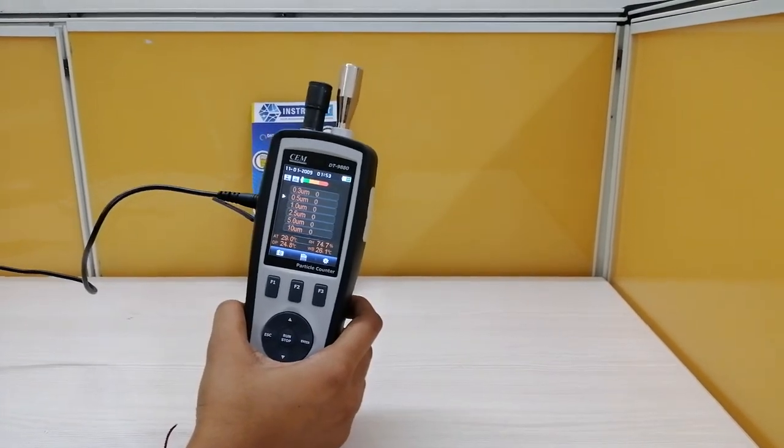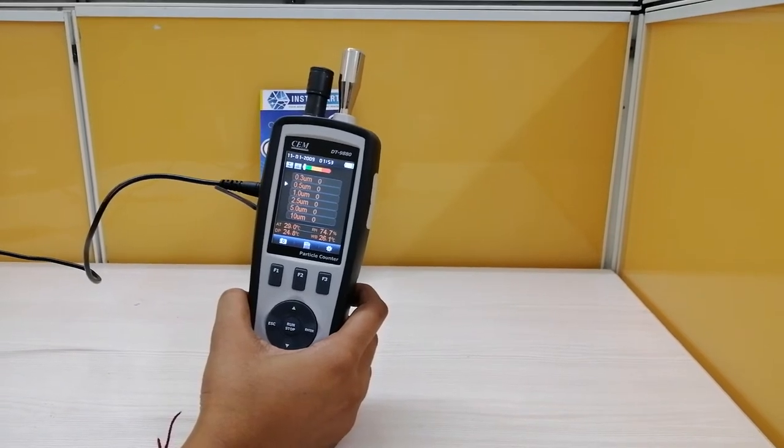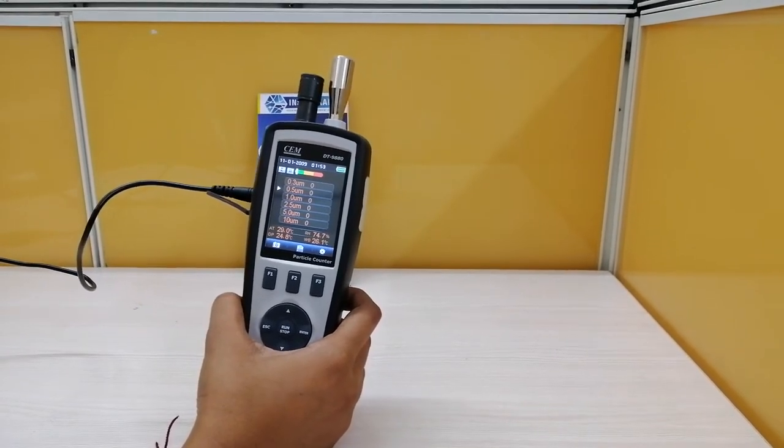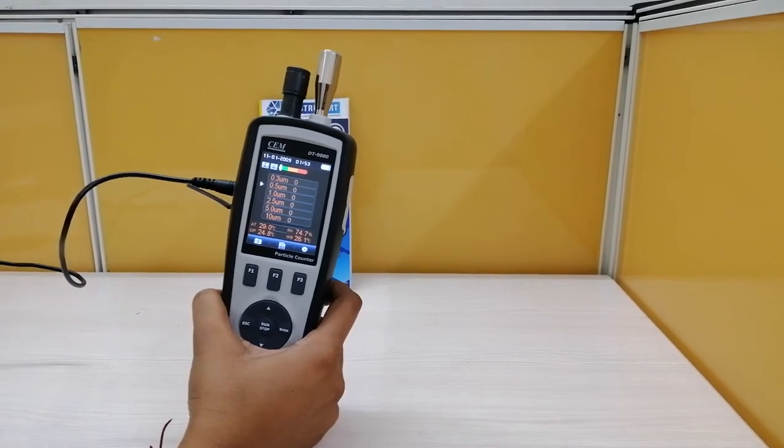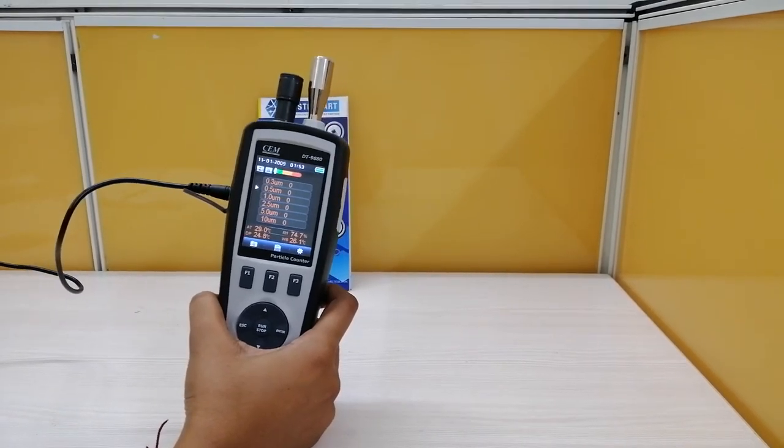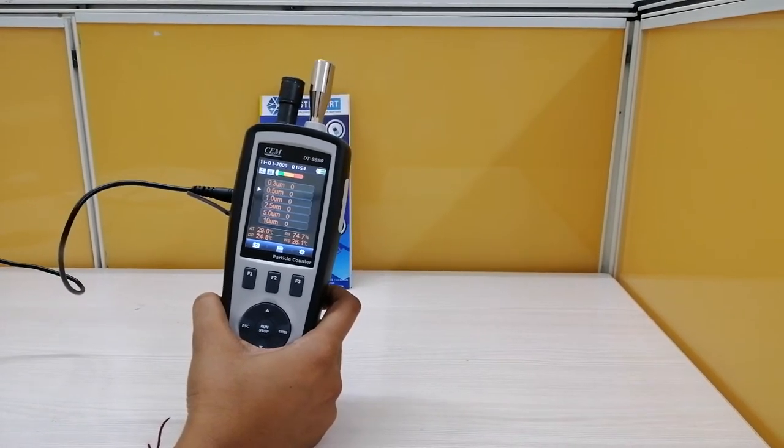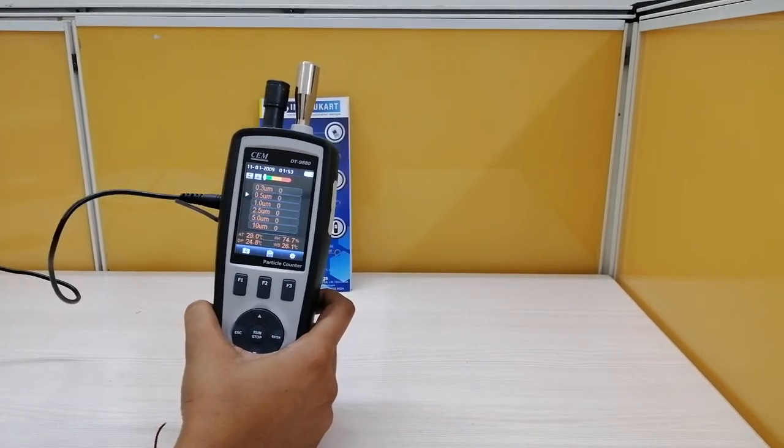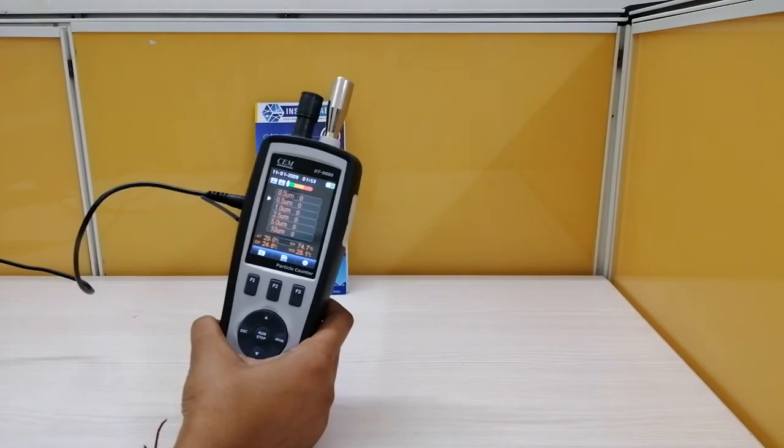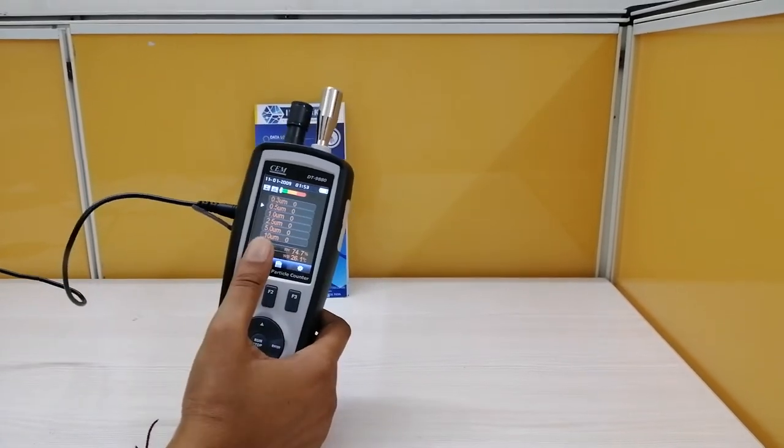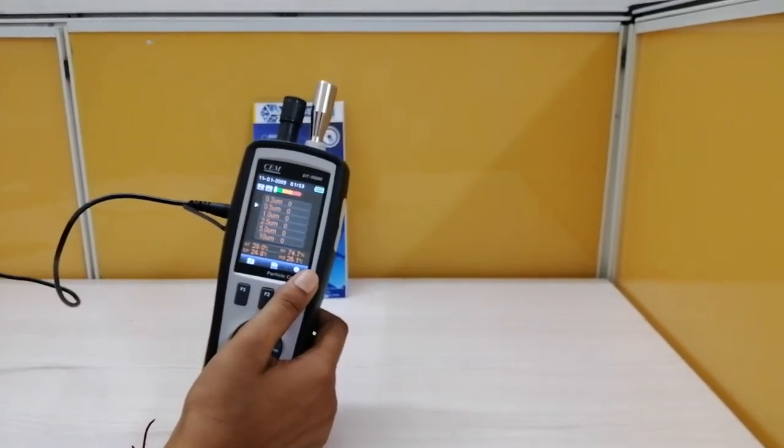This particle counter can measure in three different types of sampling modes: cumulative, differential, and mass concentration. Based on your application, you can choose the sampling mode. But let me explain what is cumulative sampling mode. When viewing the data in cumulative mode, the number or the counts associated with each channel size is the number of particles that the instrument counted for that size and greater.